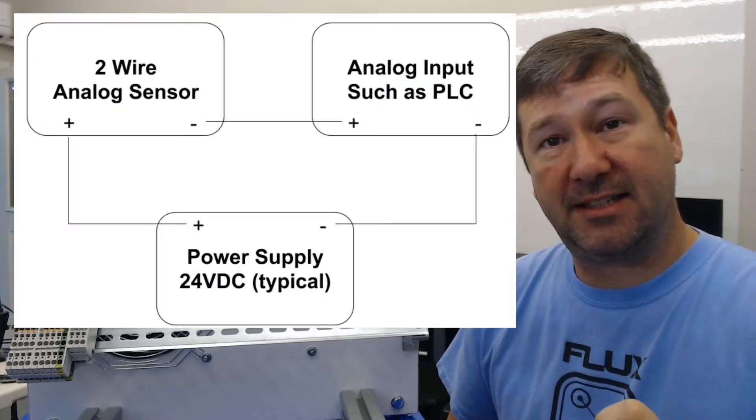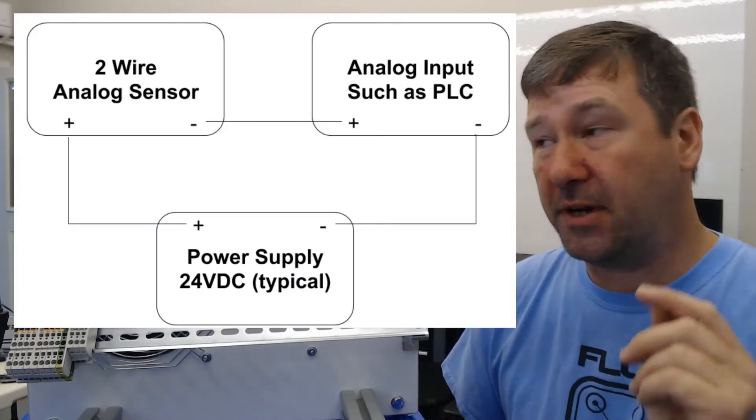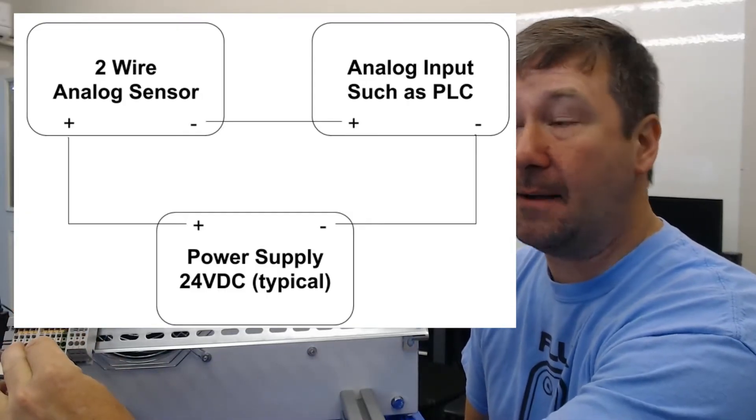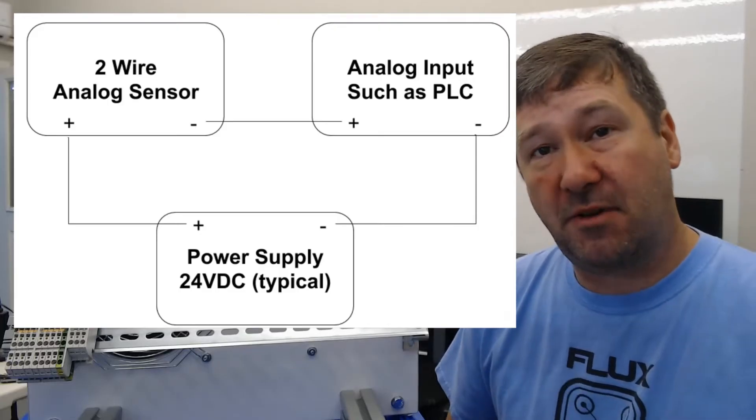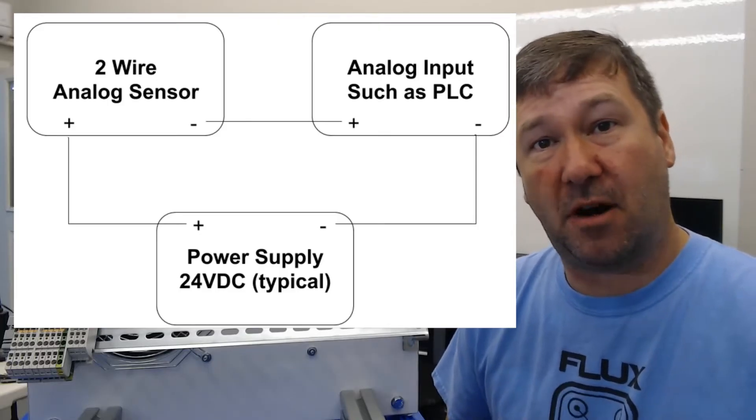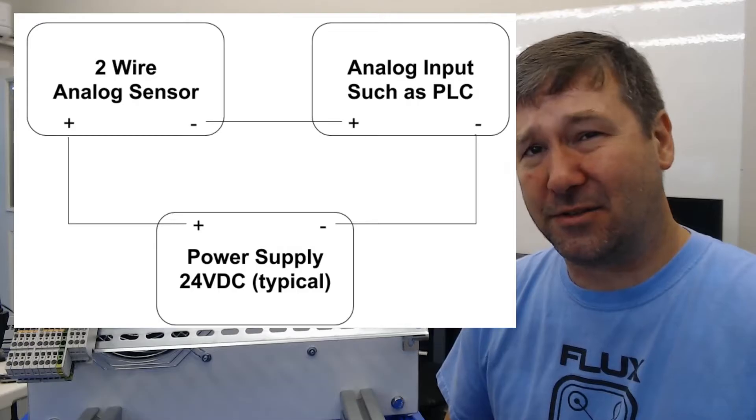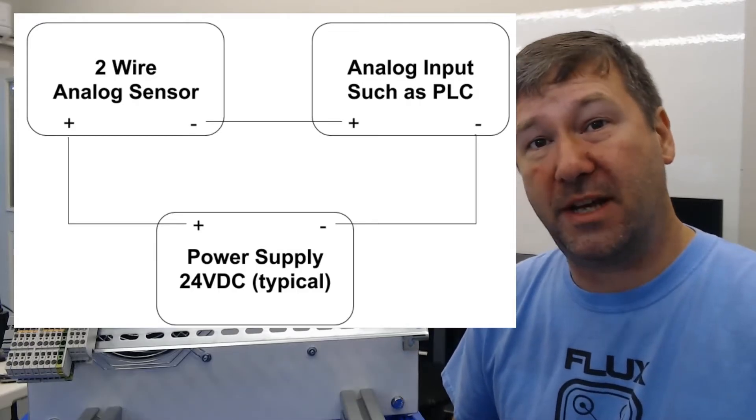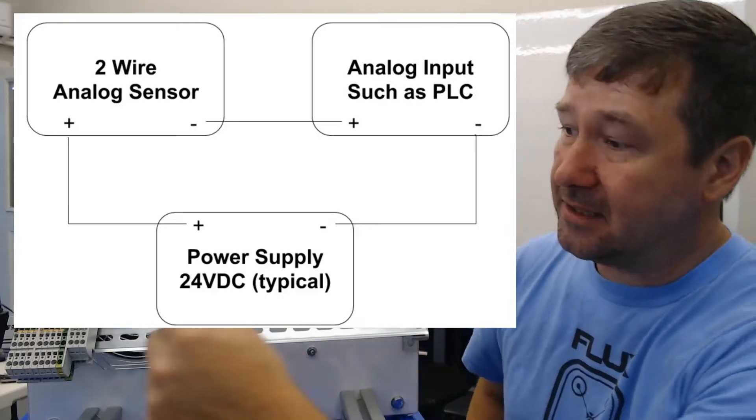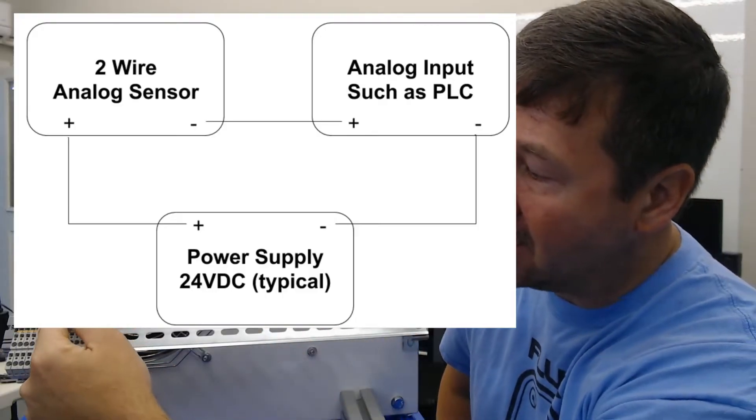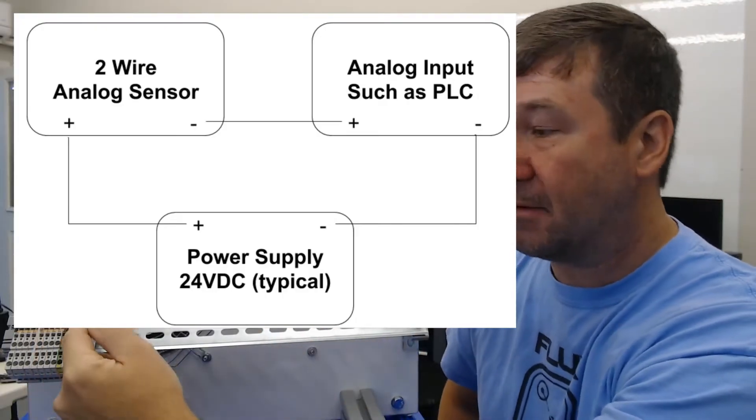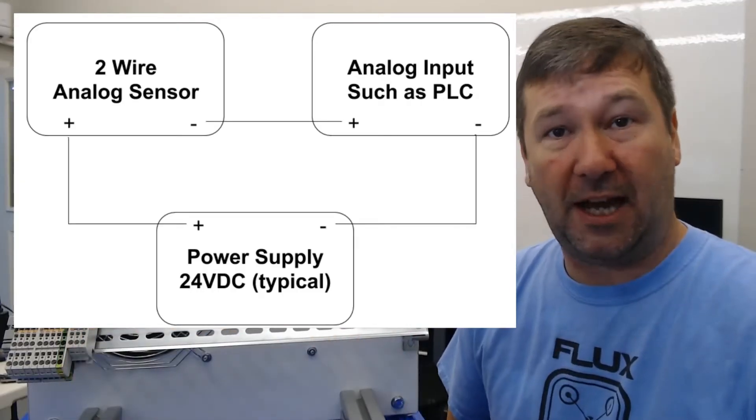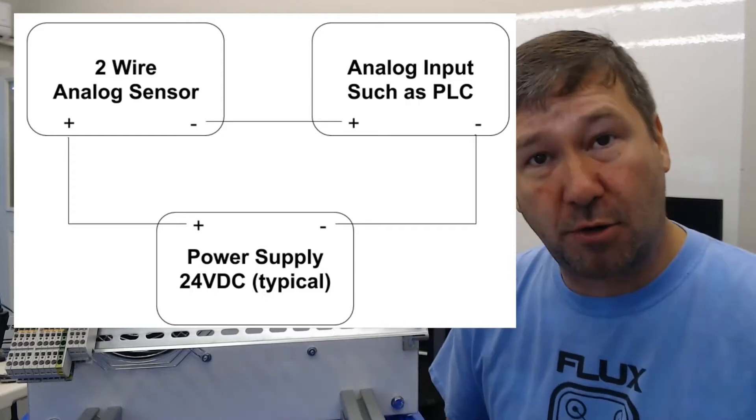This is the circuit for our current 2-wire device. We have a power supply, which in our case is going to be our 24-volt power supply. Then we're going to go from the positive of our power supply to the positive of our instrument. Here's where it gets a little tricky. From there, we're going to go from the negative of our instrument to the positive of our PLC input, or in our case the positive of our meter. Then we're going to go back out of the negative of our meter to the negative of the power supply, and that will make our current loop.